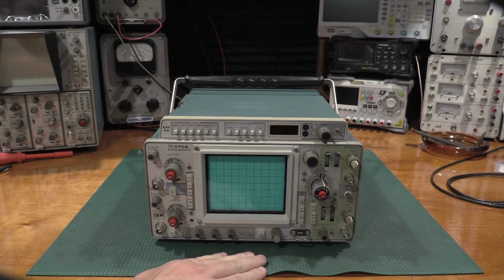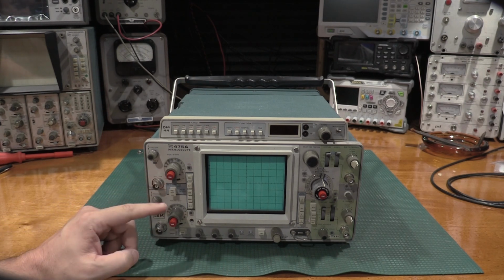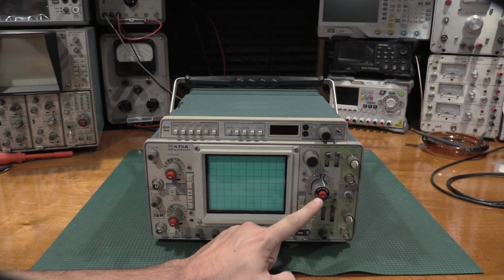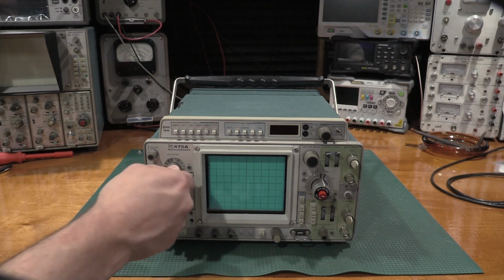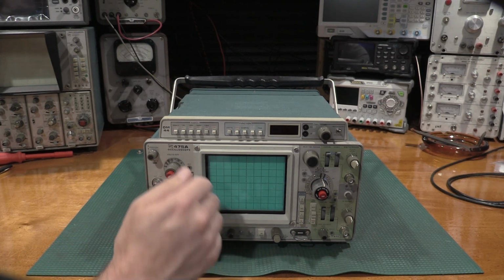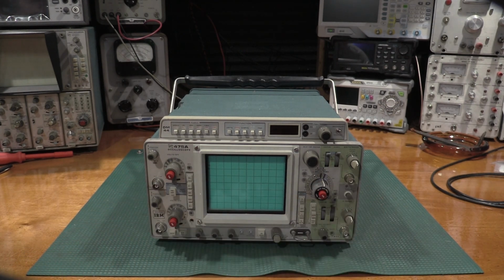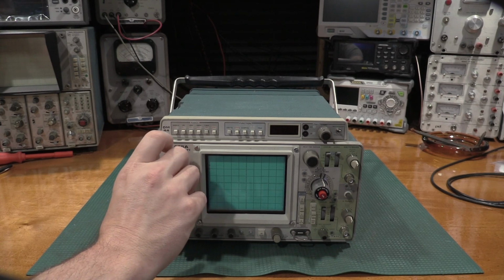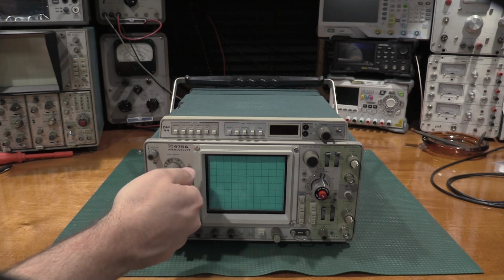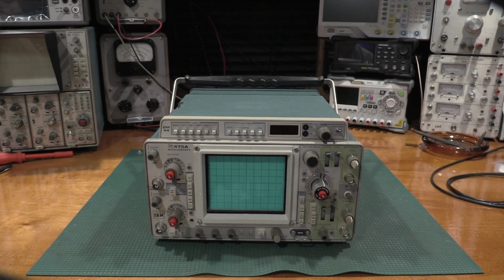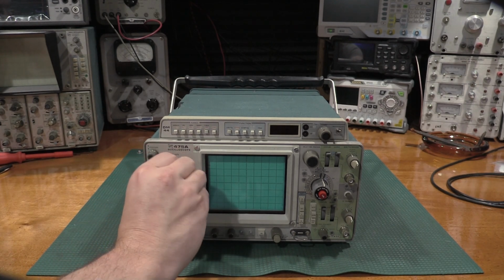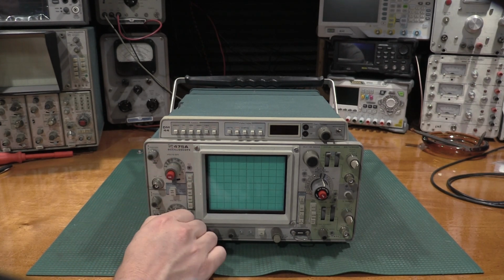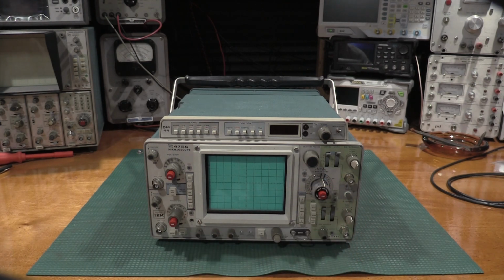Since I'm just glossing over it and I notice it, the other thing is the VAR controls are all correctly oriented. If any of the VAR controls are flipped over, spun around like that, that means it's not in the calibrated detent. And the variable controls are an attenuator too, so it can be all the way down and you wouldn't notice it. So you want to take the red knobs and rotate them all clockwise till they click.